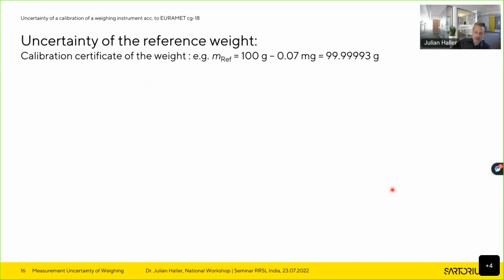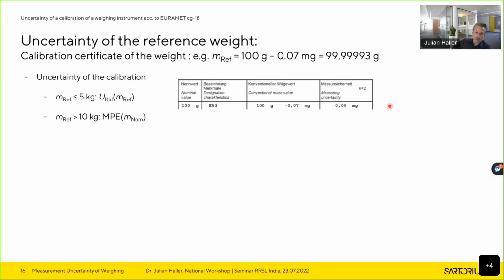Now, the next contribution, as mentioned, is the uncertainty of the reference weight. And again, you might say, well, I have a calibration certificate for my weight, so what is the uncertainty? Now, let's start with the obvious thing. If you calibrate a weight, you will also have a measurement uncertainty. And that is what you see, for example, on the calibration certificates that we issue.